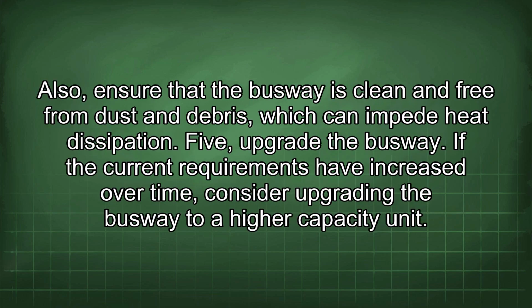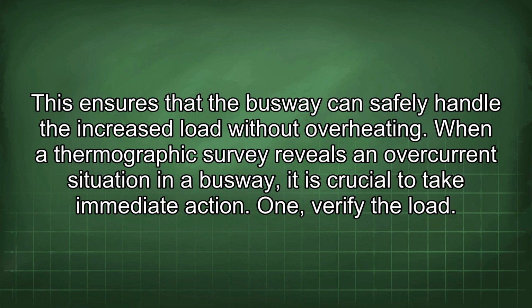Also, ensure that the busway is clean and free from dust and debris, which can impede heat dissipation. 5. Upgrade the busway. If the current requirements have increased over time, consider upgrading the busway to a higher capacity unit. This ensures that the busway can safely handle the increased load without overheating.